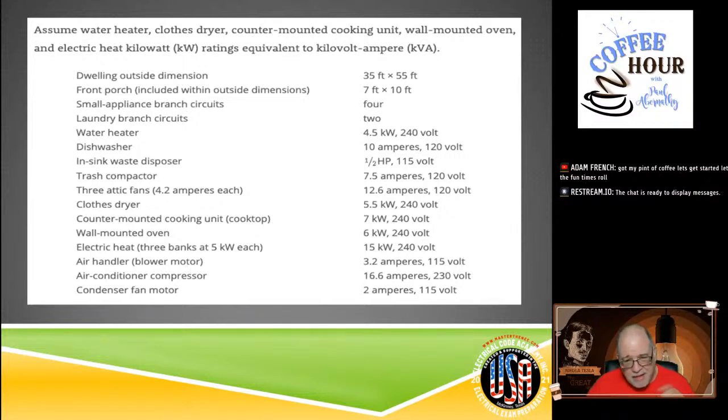Now, remember the nameplate values on a lot of these motors? We refer to that as FLA. It doesn't say that in the code, but we say that's full load amps. The reason we're trying to distinguish the difference is that's the value on the motor. We typically use that for overloads, and there are some allowances where we would use that for certain things in 430.22. But in reality, what we're trying to find now is the FLC, full load current. And that's why we're going to go to 430.248 for that. Put a mark in there because you're going to have to come back. Okay, so we got that one.